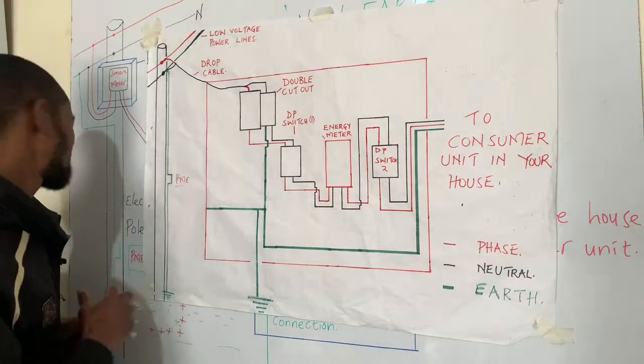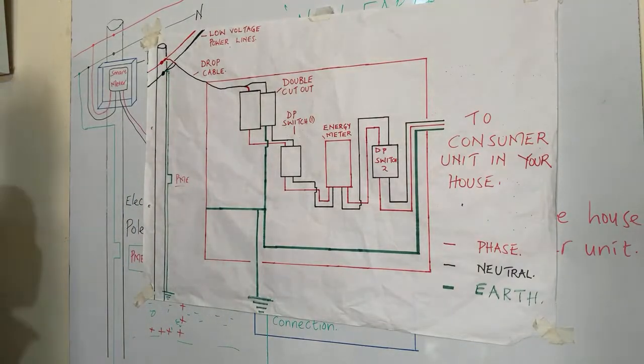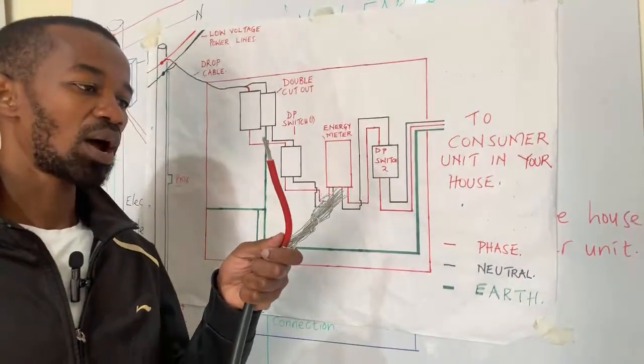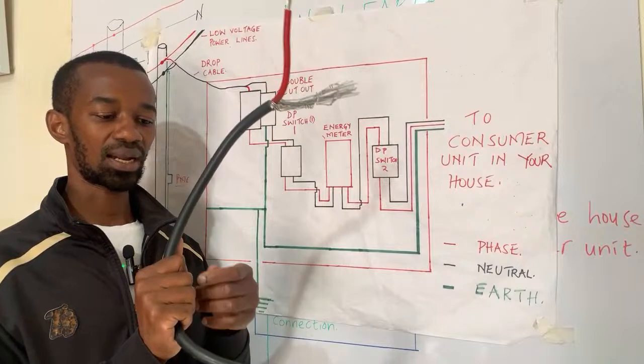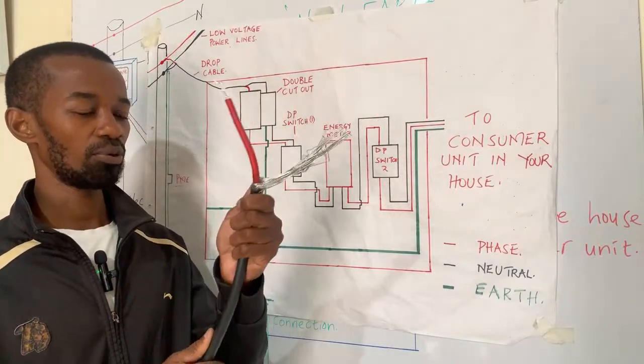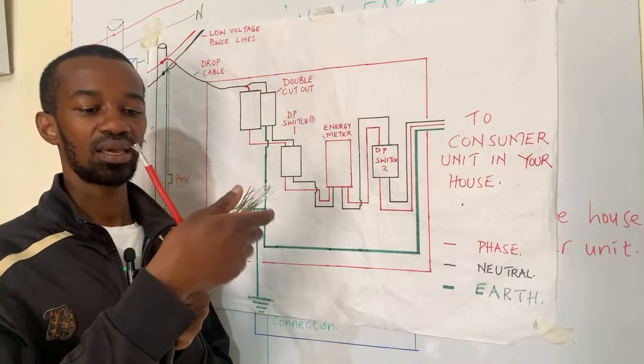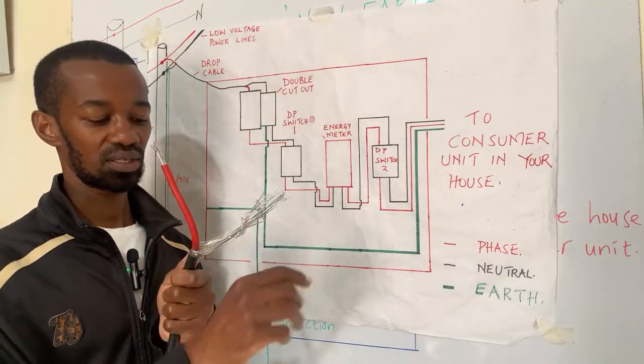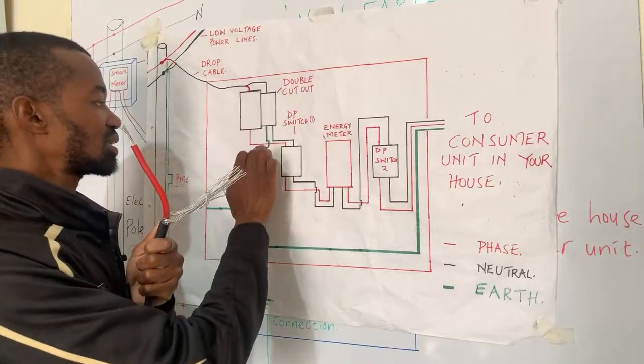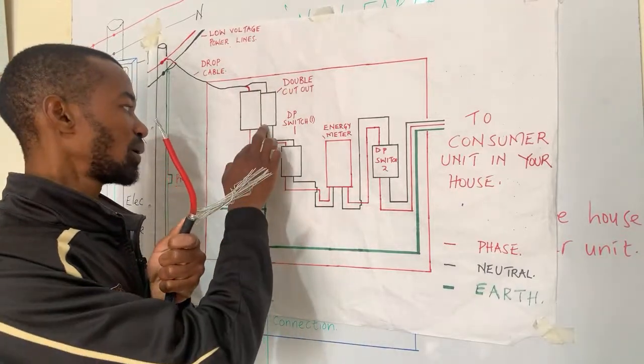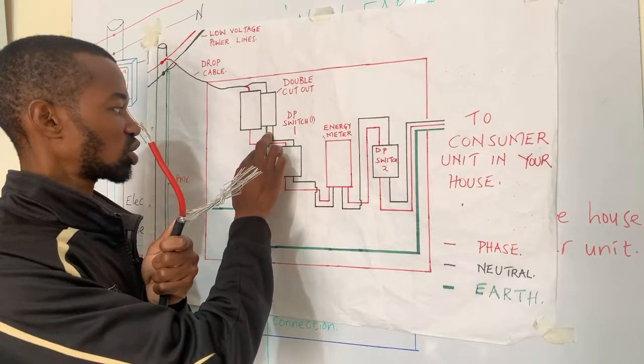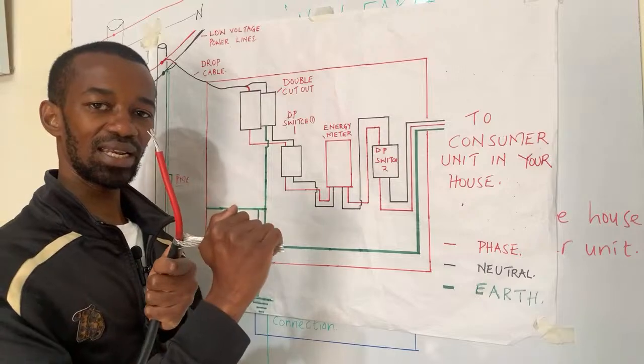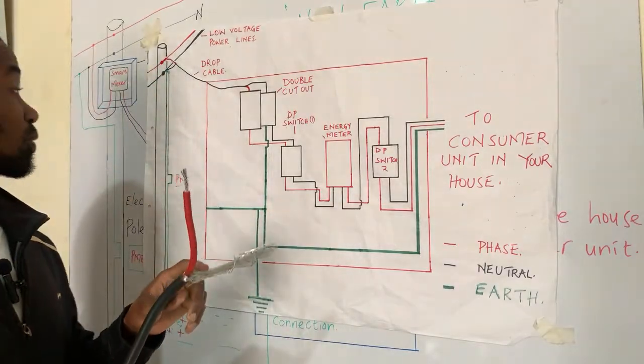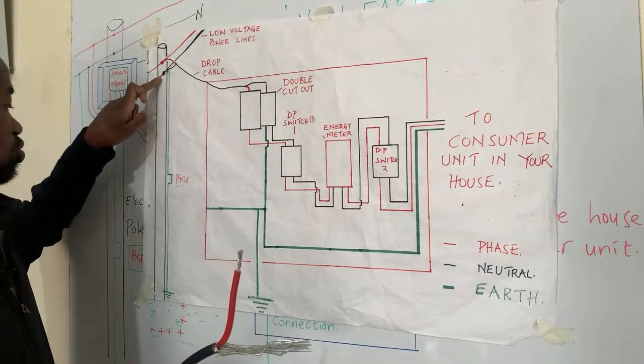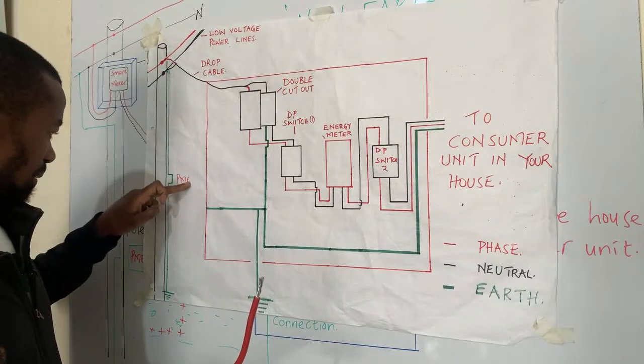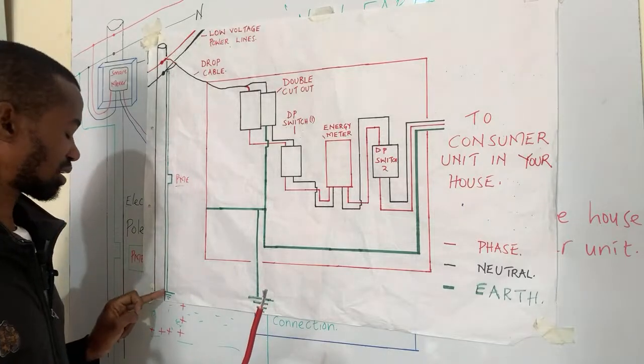So the drop cable still will drop with only two connections, or two wires inside. This is a black drop cable. The cable has two cables inside, where we have the phase and we also have this. So this one, when it comes here, you will still loop it at the neutral connection. So it will again be in contact with this conductor here, the neutral, as well as the PME that is dropping to the ground for earthing purposes.